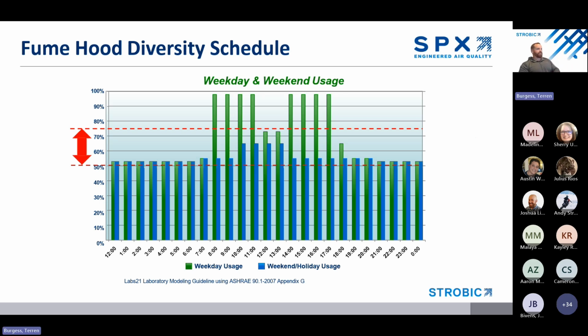So I spoke to this in the previous slide, but when we talk about diversity, we mean recognizing that not every lab space, fume hood, or exhaust device will be operating at its maximum flow at the same time. So in practice, and the image here demonstrates this, usage varies throughout the day, right? Some hoods are closed, some labs are unoccupied, and some processes are only running intermittently. So if we were to size our exhaust and supply systems as if every single piece of equipment was at full load 24/7, we're going to end up with a massive over-design.